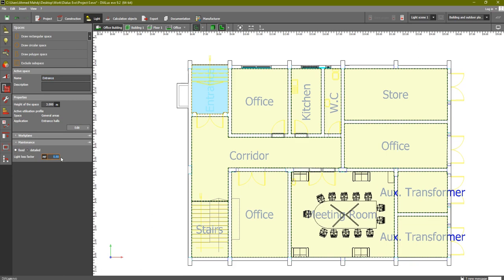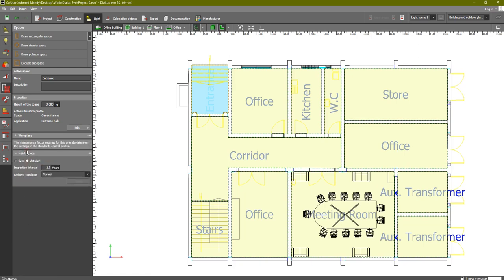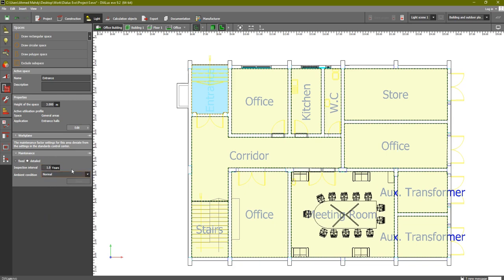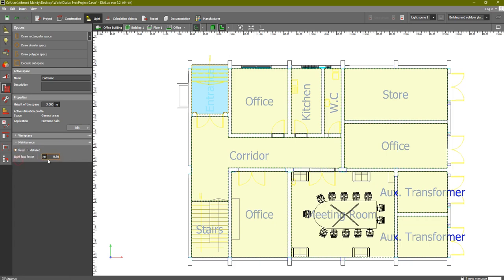Go to Maintenance and you will find the maintenance factor, which has a default value of 0.8 — as discussed, for indoor spaces we select 0.8. Under Detailed Values you can set the number of years and the cleanliness condition: very clean, clean, normal, or dirty. However, for simplicity we usually put it as a fixed value of 0.8. That completes the entrance room settings.